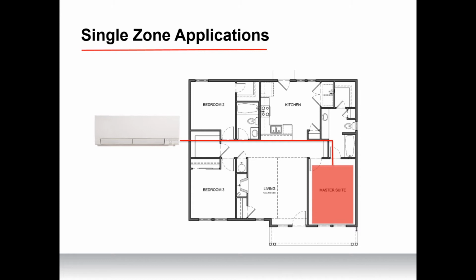Why is the master generally the most common application for a single zone? In most builds, the master is usually, if it's a 2-story, on the 2nd floor, maybe partially over a garage. If it's a ranch, it might be the furthest away from the furnace, furthest away from the air handler, so it's on the longest duct run. It's getting the worst amount of airflow, and it's where the owners of the home spend the most amount of time. So this is the room that if it's uncomfortable, it's the one that people really want to take care of. So a single zone application is really prevalent in master suites.